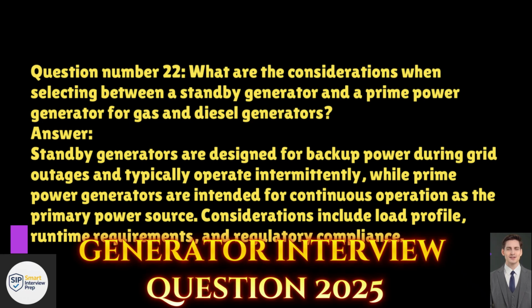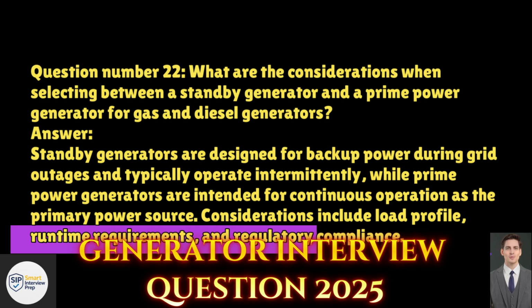Question 22: What are the considerations when selecting between a standby generator and a prime power generator for gas and diesel generators? Answer: Standby generators are designed for backup power during grid outages and typically operate intermittently, while prime power generators are intended for continuous operation as the primary power source. Considerations include load profile, runtime requirements, and regulatory compliance.